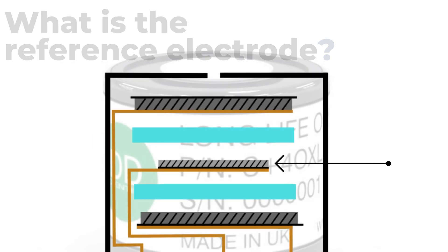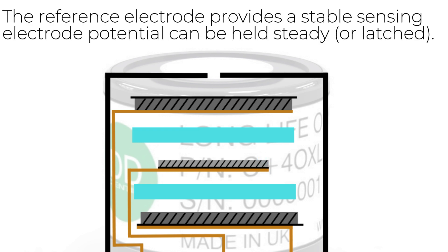The third electrode inside the sensor, the reference electrode, does not take part in any chemical reactions and is included only to provide a stable potential or voltage against which the sensing electrode potential can be held steady or latched.